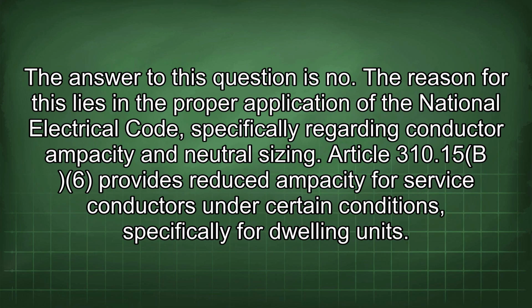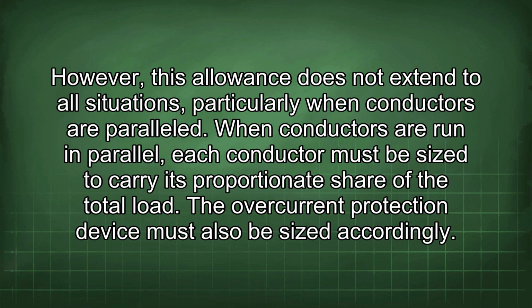The reason for this lies in the proper application of the National Electrical Code, specifically regarding conductor ampacity and neutral sizing. Article 310.15(B)(6) provides reduced ampacity for service conductors under certain conditions, specifically for dwelling units. However, this allowance does not extend to all situations, particularly when conductors are paralleled. When conductors are run in parallel, each conductor must be sized to carry its proportionate share of the total load. The overcurrent protection device must also be sized accordingly.